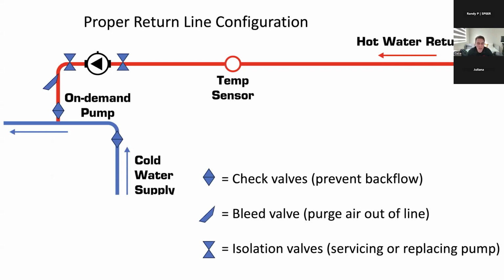Now, when hot water comes into your supply line, it will naturally come out of your fixtures, out of your shower or your faucet, and you can actually see the air getting purged out. It basically coughs air. But when that air finds its way into the return line, because you have a check valve on the return line, there's no backflow, right? So that air just gets stuck in there. And then when the pump is running, it's not actually able to move water. So what you have to do is install what we call a bleeder valve.